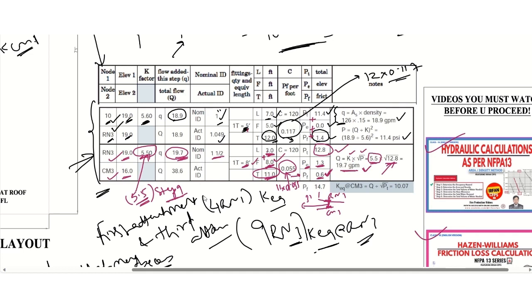And elevation will be 1.3 PSI. How we got this one? There is one formula: for 1 foot elevation, 0.433 PSI will be the value. So since we have 3 feet, 19 minus 16, we are getting 3 feet. So for 3 feet if you multiply this with 0.433 PSI, then we are going to get 1.3. And PT will be 12.8. So you need to remember all these things, or at least if you have this example, I believe you can do any kind of calculation by keeping this in front of you. So now we already got everything whatever we required. Finally, what we are doing, we are adding this PT plus PE plus PF. Since already this PT is from the above, we already got 12.8. Now we will add with 1.3 and 0.6, so we are going to get 14.7.